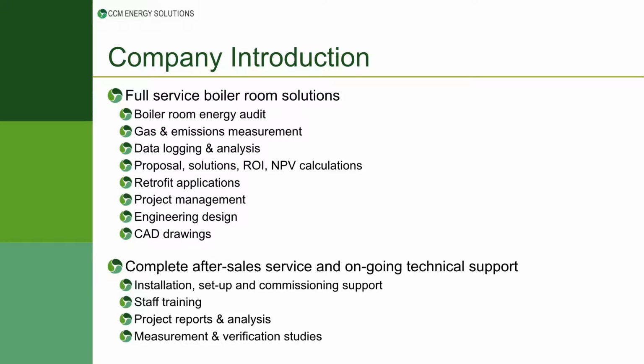So my company started out in 2008 as a boiler room energy service company. We started to do energy audits, looking at the existing setup on site. We go into a plant room, we'd record gas usage, electricity usage, measure the emissions for the existing setup, and measure cycling efficiency, how often systems are turning on and off. From that data, we do our logging to see what we think we'd be able to achieve with that existing setup. And what we do is retrofit equipment onto existing boilers, existing burners, if they can run efficiently.